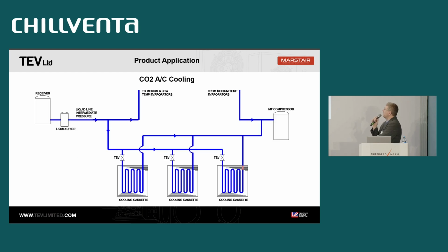So on the cooling side, they're similar to how you do the medium temperature cabinets. You have the receiver, which is like the intermediate pressure receiver. They're normally after a liquid dryer. You would split off towards the ceiling cassettes, and then the gas from the ceiling cassettes would go back to the MT compressor.